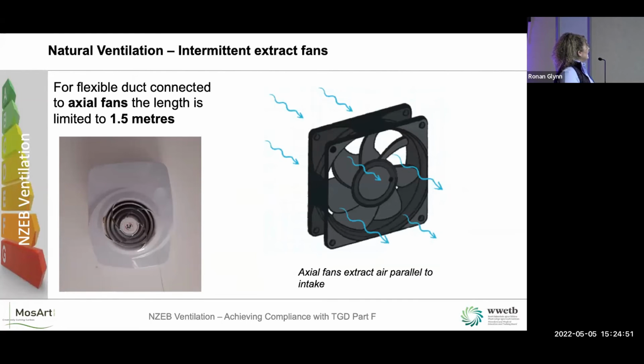This is an axial fan, but it's in the ceiling. So the ceiling, the warm, moist air is up closer to the ceiling. So now this fan is trying to pull the warm, moist air down and get it in to where the fan is. So that's not the right place for that fan.